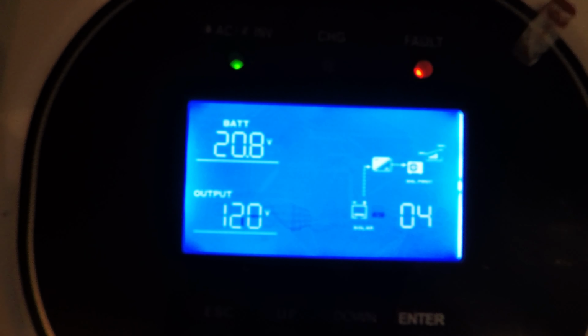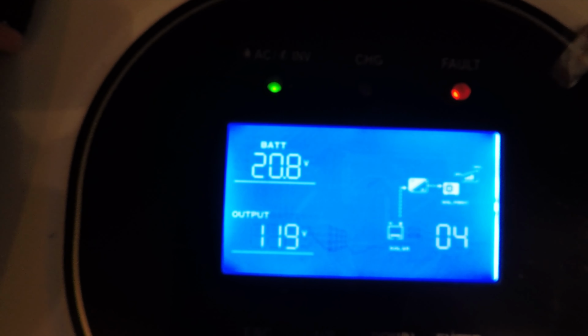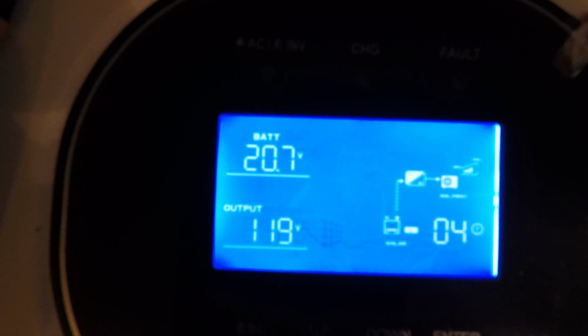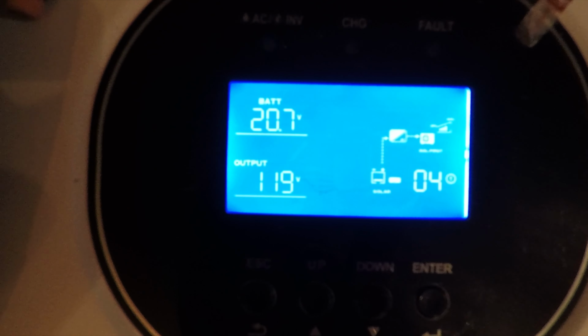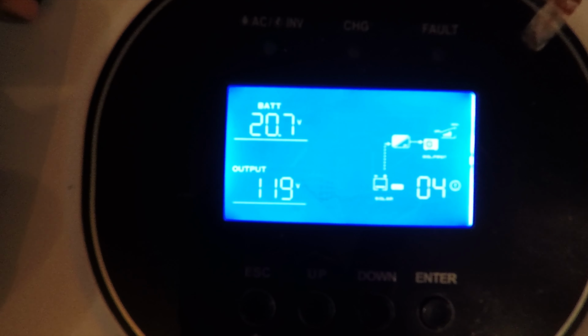I have the voltage cutoff at 20, which is zero capacity for a 24 volt lithium pack, so it should be coming down fast during this last bit. As soon as that inverter hits 20 volts, it's going to go into alarm and turn off. Alarm 4 - I'll have to look that up in the manual.